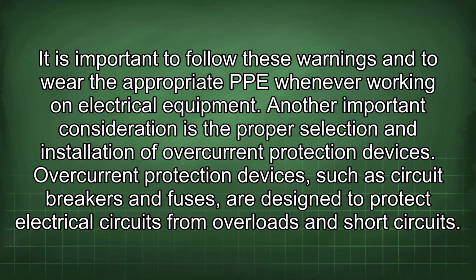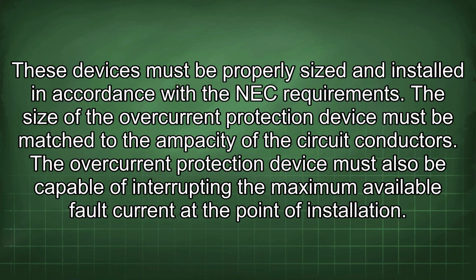Overcurrent protection devices, such as circuit breakers and fuses, are designed to protect electrical circuits from overloads and short circuits. These devices must be properly sized and installed in accordance with the NEC requirements. The size of the overcurrent protection device must be matched to the ampacity of the circuit conductors. The overcurrent protection device must also be capable of interrupting the maximum available fault current at the point of installation.